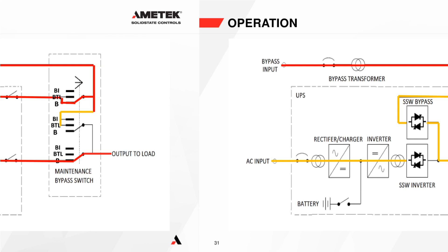Yeah. So we're in normal position on the bypass switch. We're on normal position, but we have pressed bypass to load on the static switch. So power is flowing from the bypass down here through the static switch here and out to our load circuit. So the question is, would the load be automatically switched back to the normal source if there's a loss of bypass source? AMETEK solid-state controls design principles say, no, it will not.